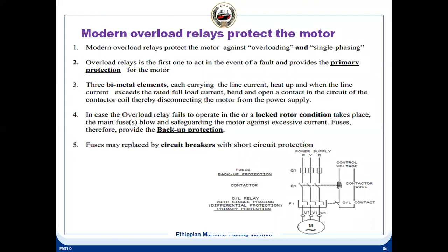Overload relays are the first to act in the event of a fault and provide primary protection to the motor. You can see in this diagram here, the bimetal elements, each carrying a line current, heat up when the line current exceeds the rated load current. They bend and open a contact in the circuit of the contactor coil, thereby disconnecting the motor from the power supply. The overload is always connected in series with the coil supply. So whenever an overload takes place, the overload opens the control supply for the contactor, the contactor opens and the motor trips.